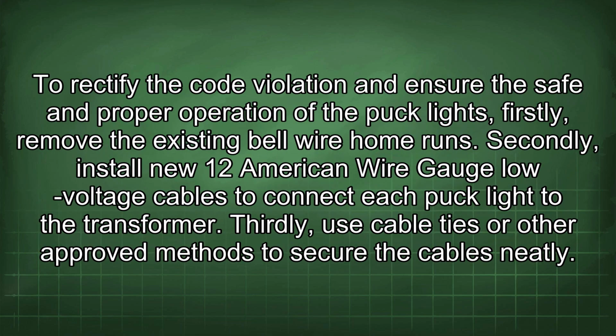To rectify the code violation and ensure the safe and proper operation of the puck lights, firstly, remove the existing bell wire home runs. Secondly, install new 12 American wire gauge low voltage cables to connect each puck light to the transformer. Thirdly, use cable ties or other approved methods to secure the cables neatly.